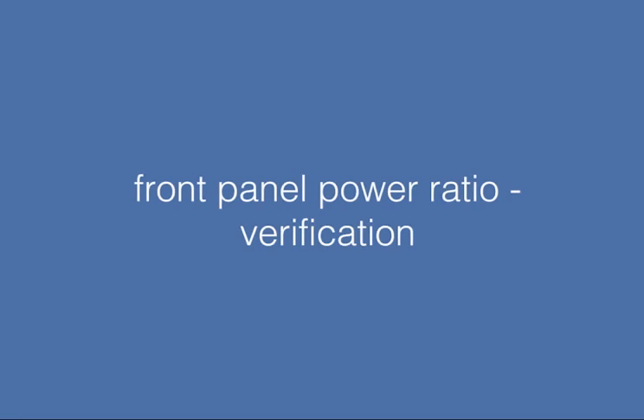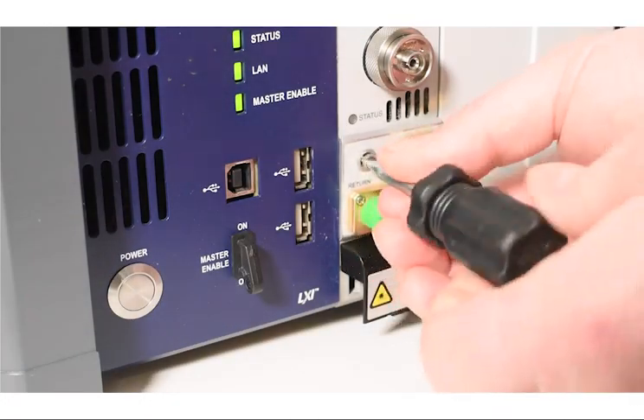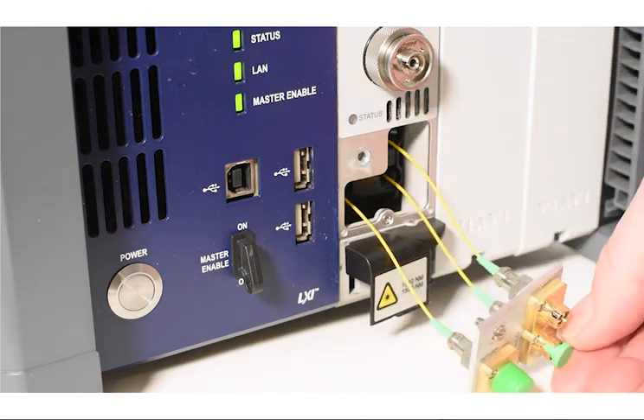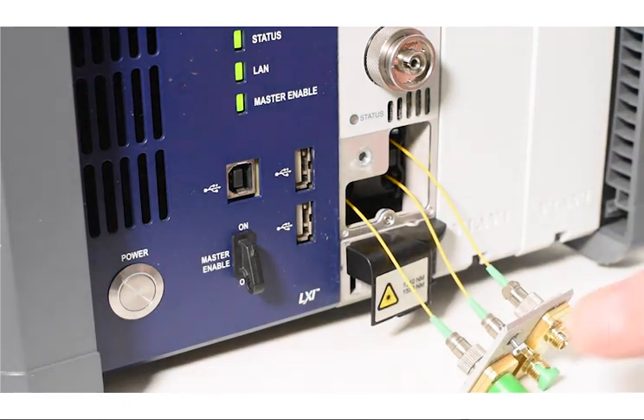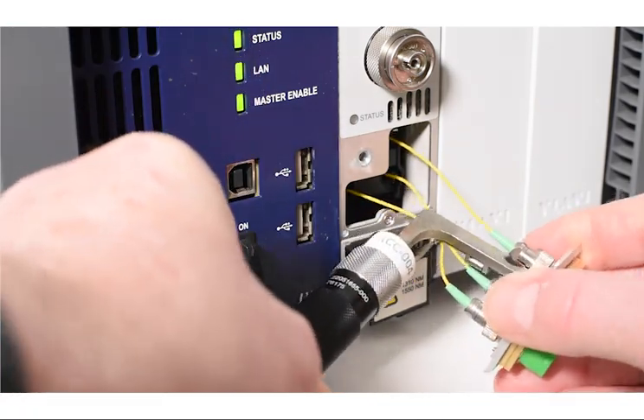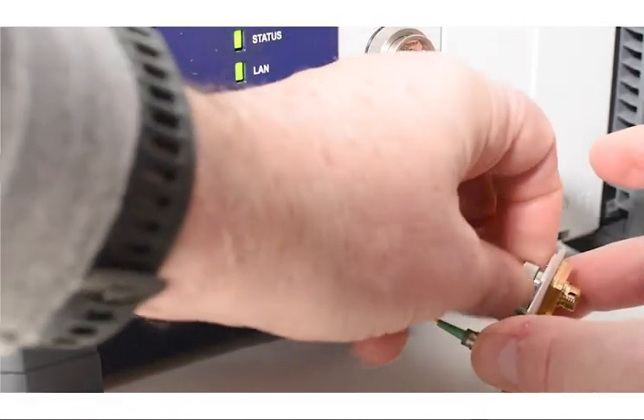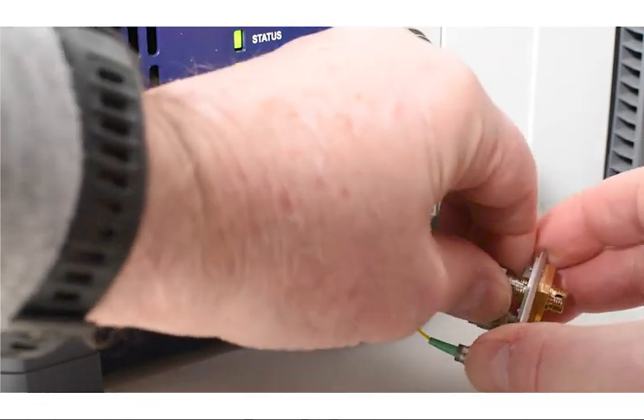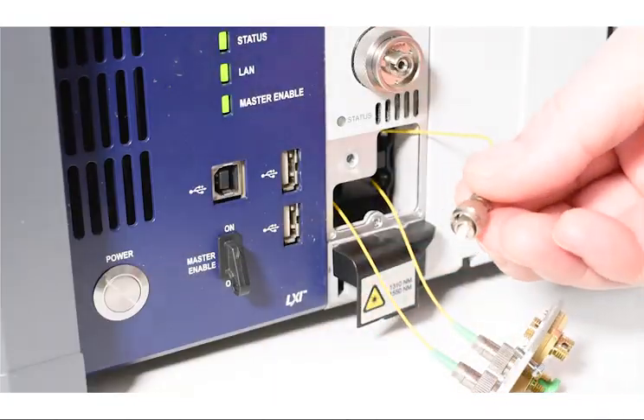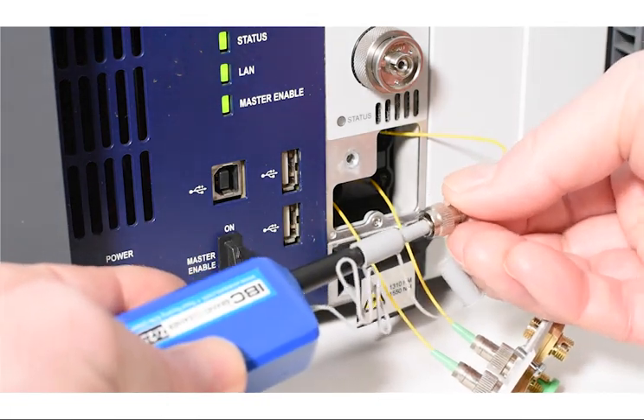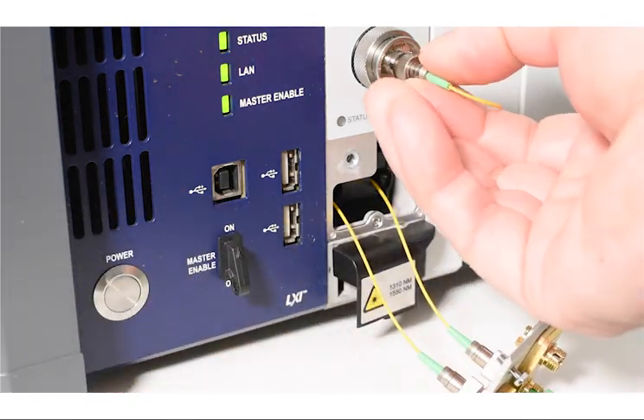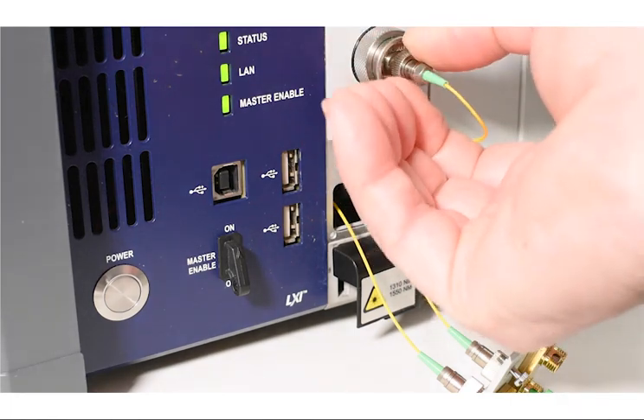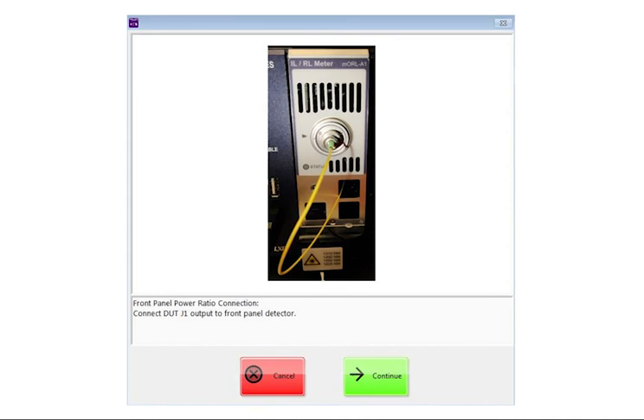Before we calibrate your system, we need to set the front panel power ratio. First step is to remove the connector panel. The connector panel should move out of the chassis without any resistance. Stop if it gets tight. Next, remove, clean, and then attach connector to the detector cap. Once the J1 connector is connected to the detector, press Continue.